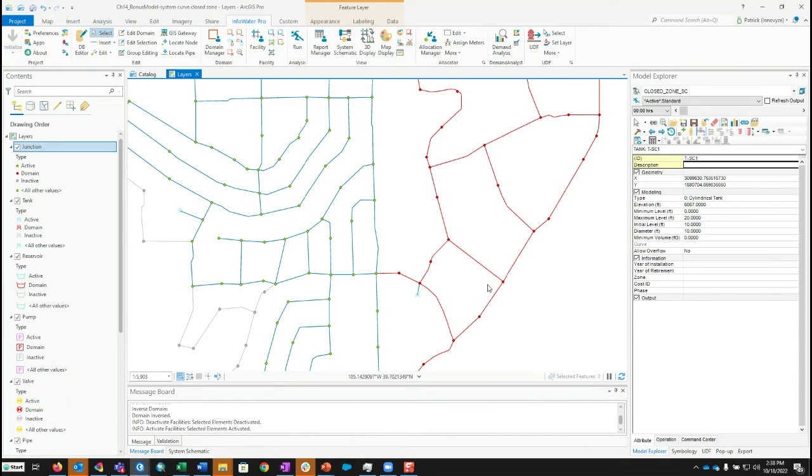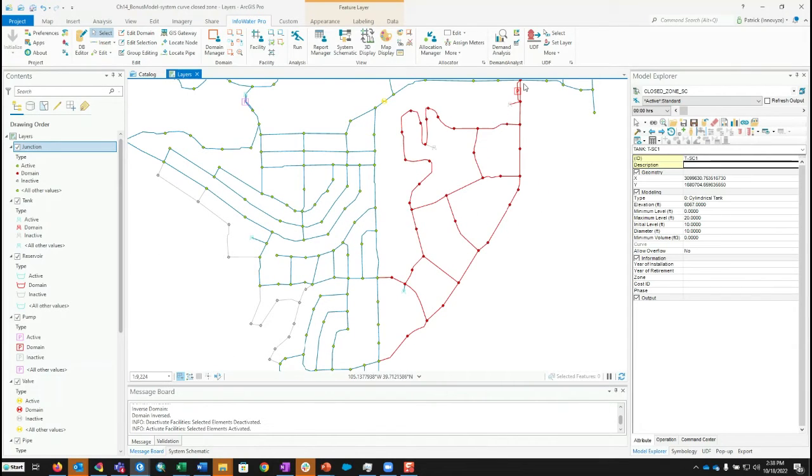I think in this case it was a little bit arbitrary, because the original pump they had here was a little bit weird, so we had to lower the HGL a little bit. Otherwise, this pump was operating very close to its shutoff, so we dropped it a little bit. But that's generally not going to be the way you're setting this hydraulic grade line.